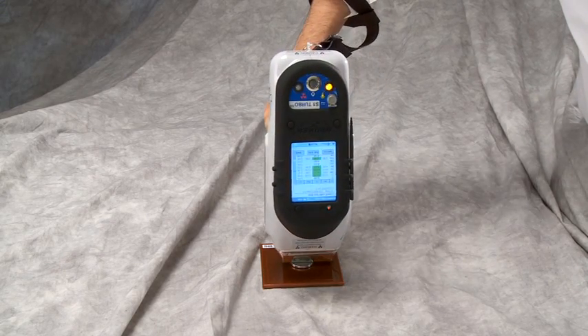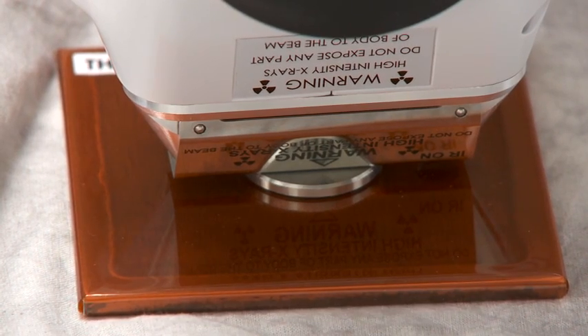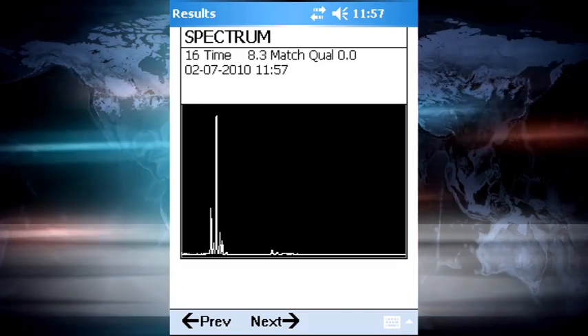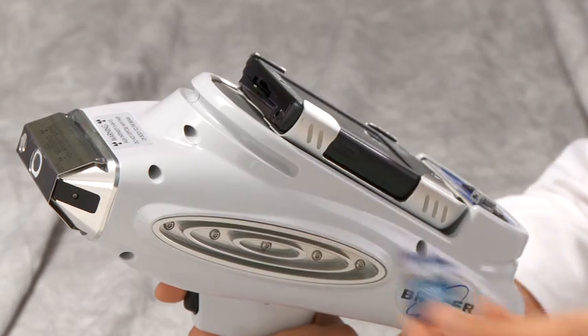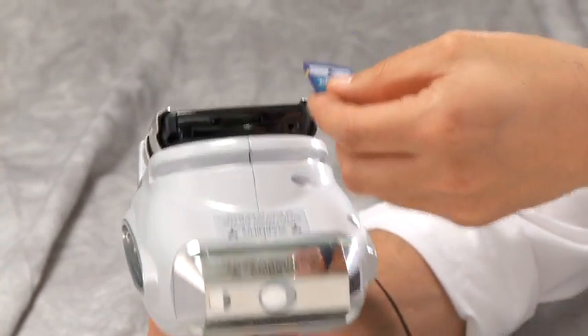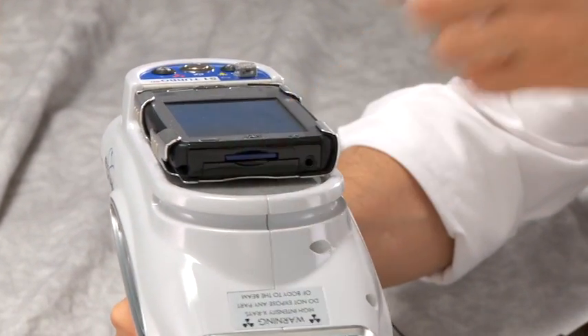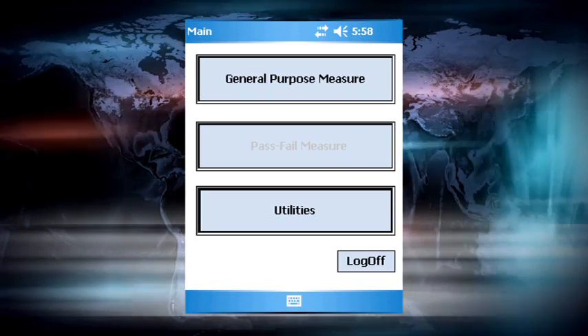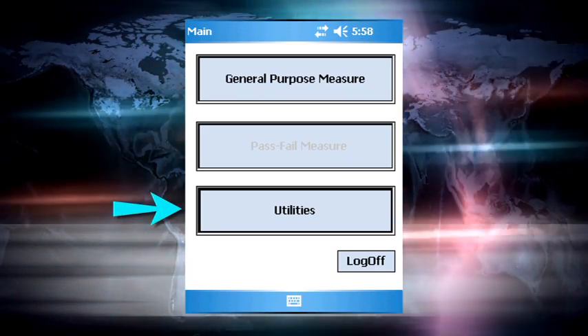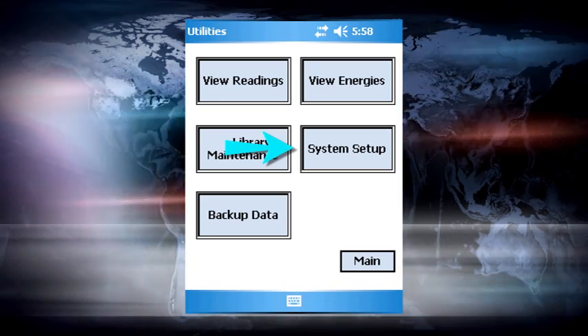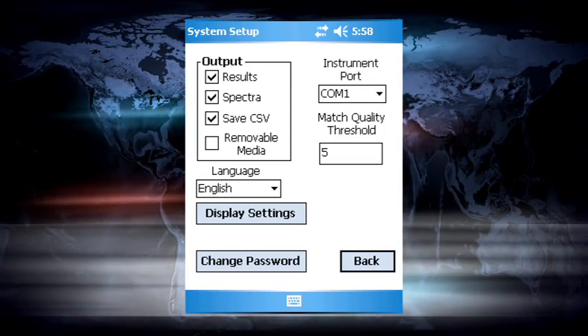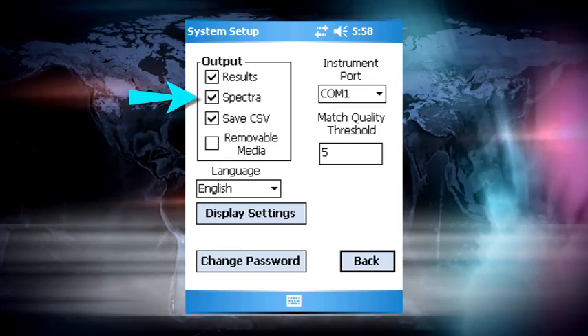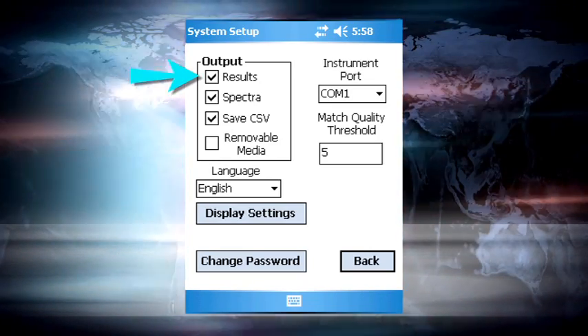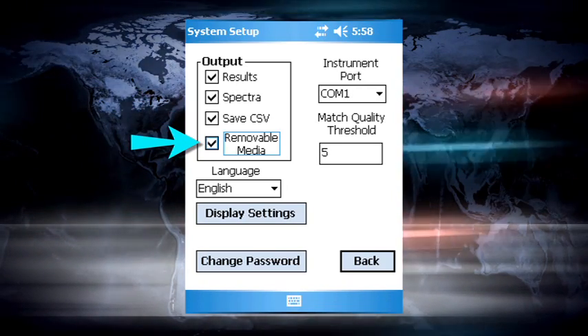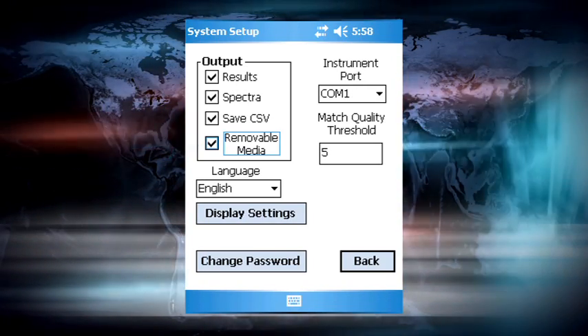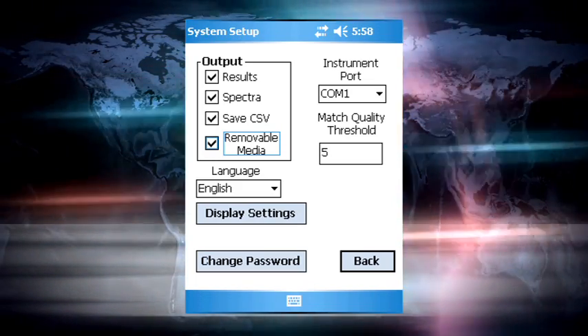There are two ways to transfer data from the analyzer. The first is to store the data on the analyzer and transfer it to a PC with the S1 software. In order to store the data directly onto the SD card, insert the SD card into the SD card slot on the PDA. Once this has been done, go to the Utility screen. Here, tap the System Setup button. In the System Setup screen, you can choose if you want to save spectra by checking the box next to Spectra. Make sure the box next to Results is checked. Finally, check the box next to Removable Media. This will result in all the data being stored on the SD card.